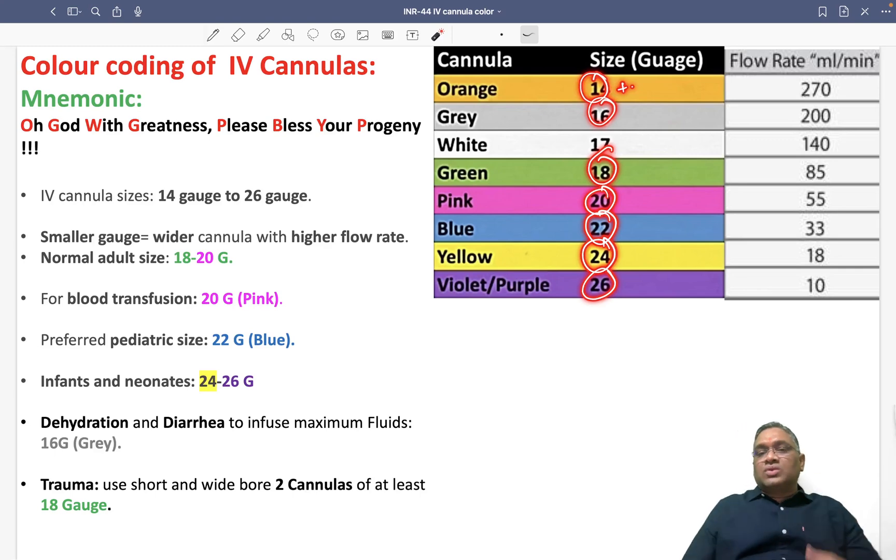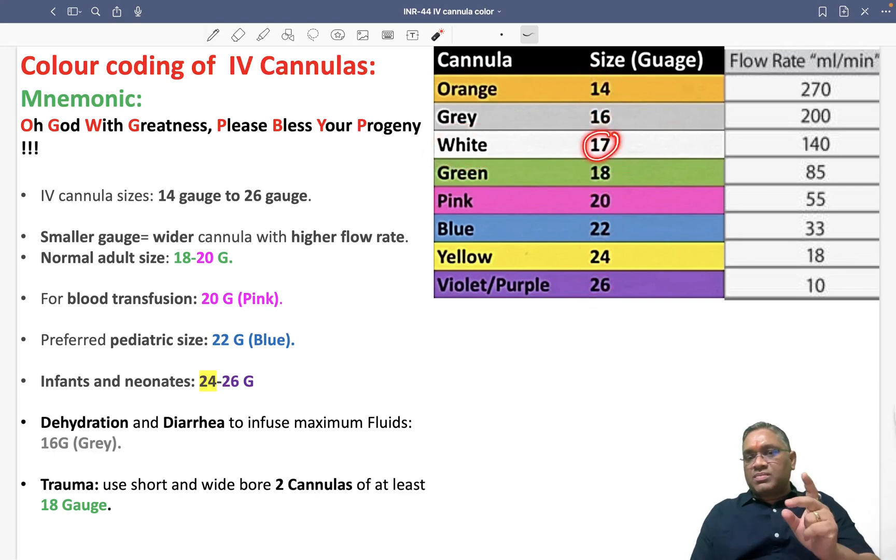There is one entry between 16 and 18 - the white color. White is the odd one at 17 gauge. You have to remember white is odd at 17, otherwise everyone has an interval of 2.